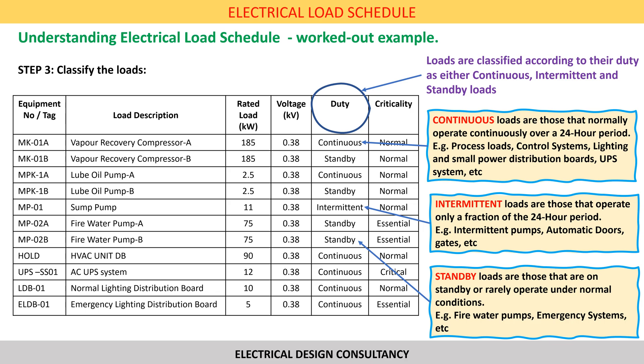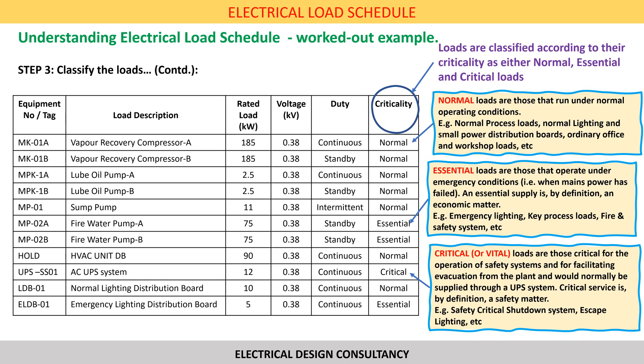Next we need to classify each load according to their duty as either continuous, intermittent or standby. Continuous loads are those that normally operate continuously over a 24-hour period; examples include process loads, control systems, lighting, small power distribution boards and UPS systems. Intermittent loads are those that operate for only a fraction of the 24-hour period; examples include intermittent pumps, automatic doors and gates. Standby loads are those that are on standby or rarely operate under normal conditions, like fire water pumps and emergency systems.